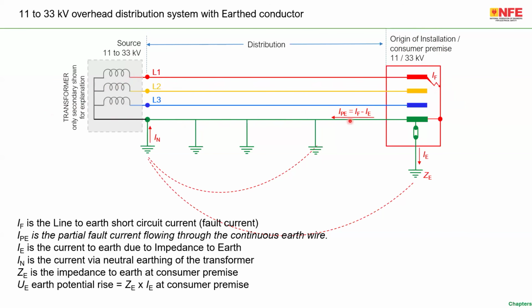IPE I put just to, as I said, I am putting this value. You cannot find IPE in the high voltage standards. I am putting it just to tell you that there is an earth conductor, a protective earth conductor, because we are explaining too much on the low voltage side and a lot of people know what PE is. So there is an earth conductor.